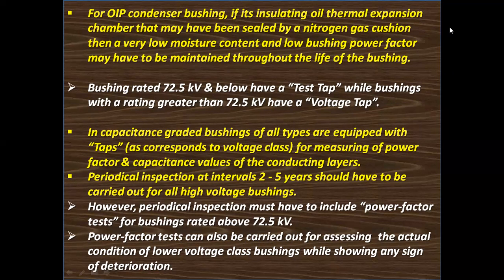Bushings rated 72.5 kV and below have a test tap, while bushings with a rating greater than 72.5 kV have a voltage tap or potential tap. Capacitance graded bushings of all types are equipped with taps, as corresponds to voltage class, for measuring power factor and capacitance values of the conducting layers.